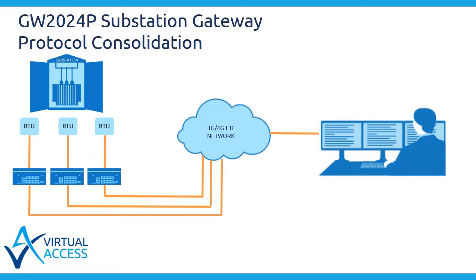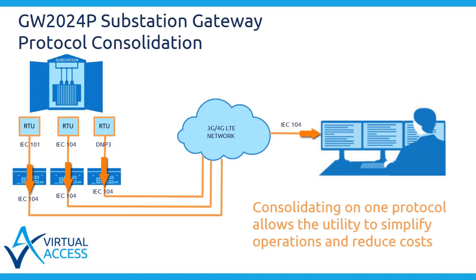The mini RTU function means that only one SCADA protocol has to be tested and maintained centrally. For example, there may be multiple RTU SCADA protocols in use, such as IEC 101, IEC 104, and DNP3. This means the SCADA master must support multiple SCADA protocols, otherwise multiple SCADA masters are needed. The virtual access solution converts protocols at the remote sites where the RTUs are located, meaning the utilities only need to maintain, test, and operate IEC 104 centrally. Consolidating on one protocol allows the utility to simplify operations and reduce costs.